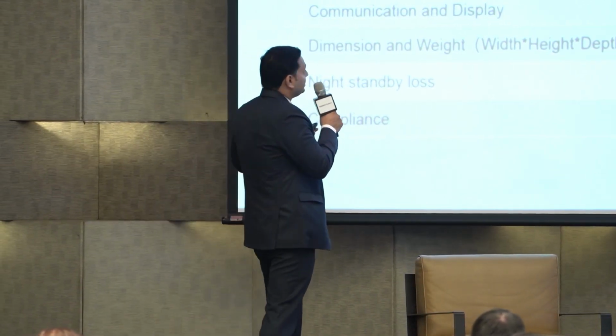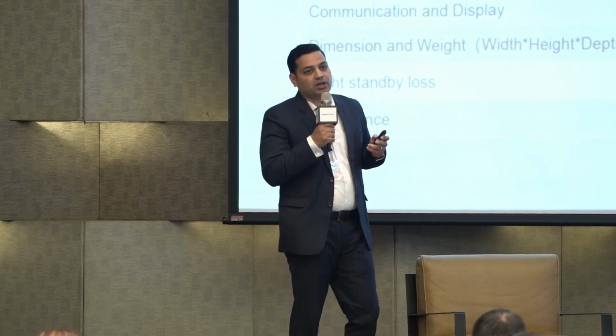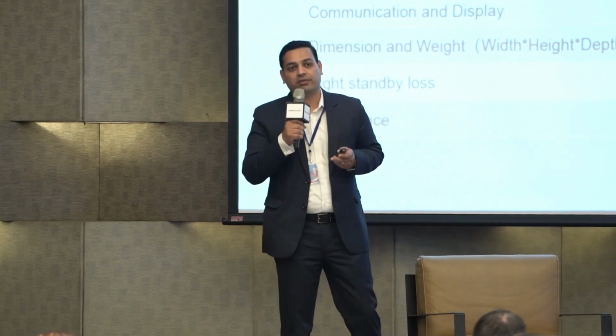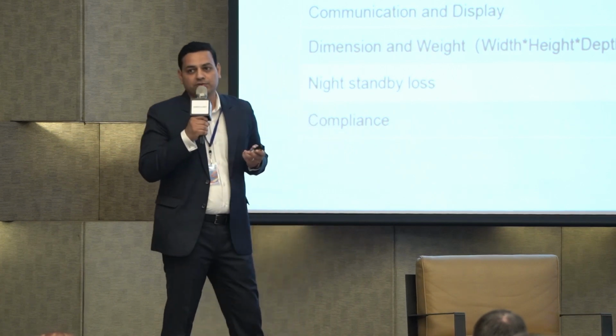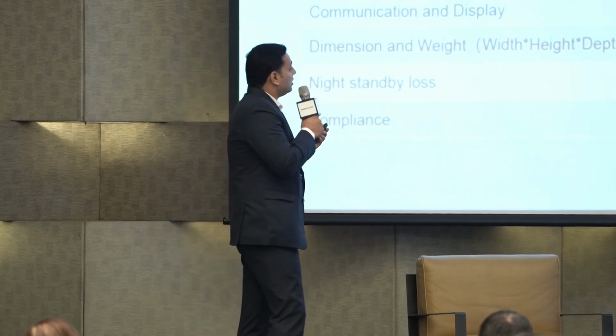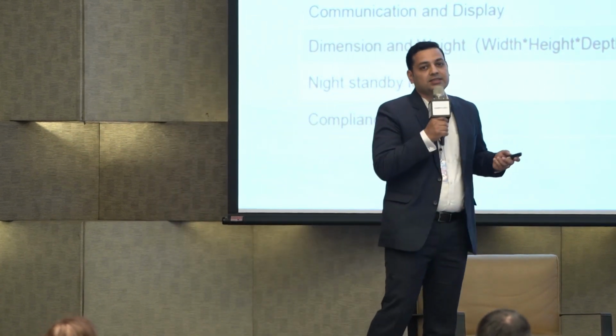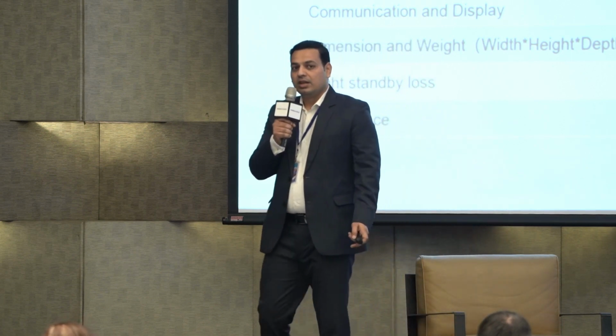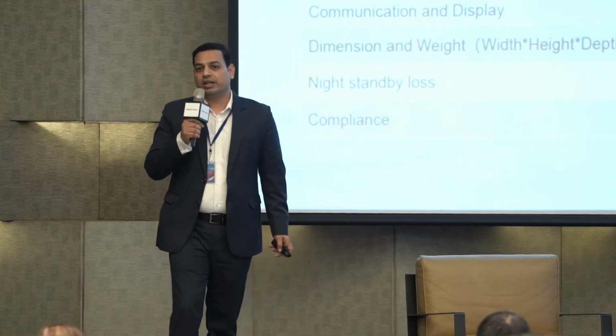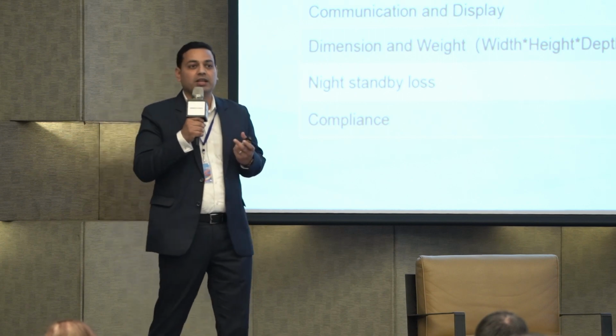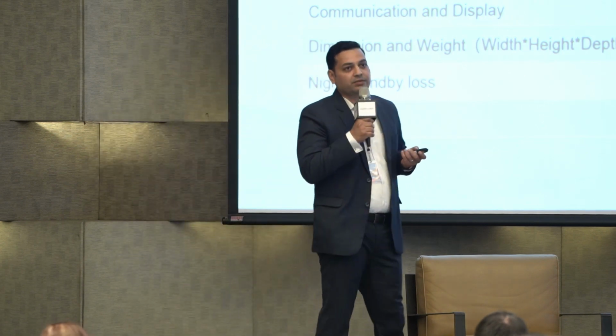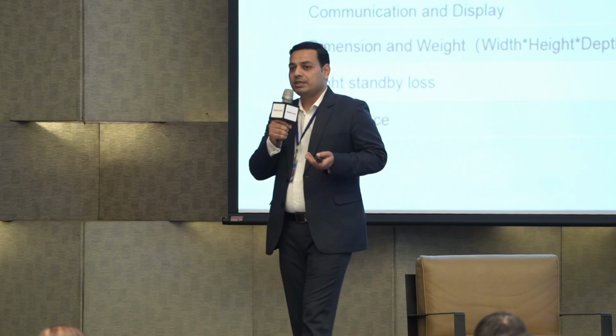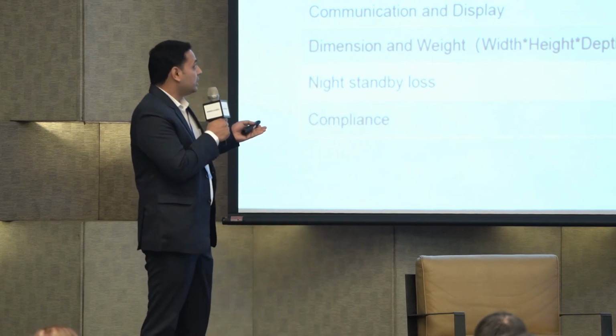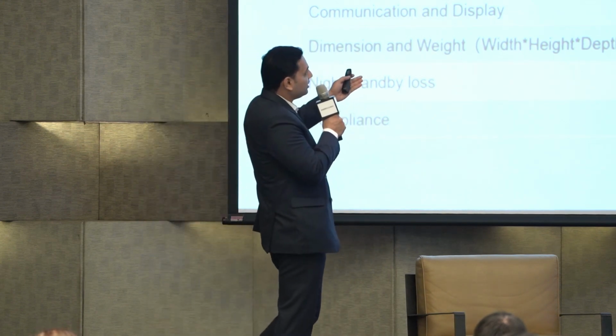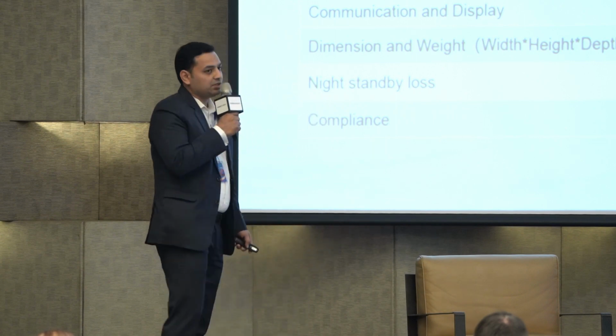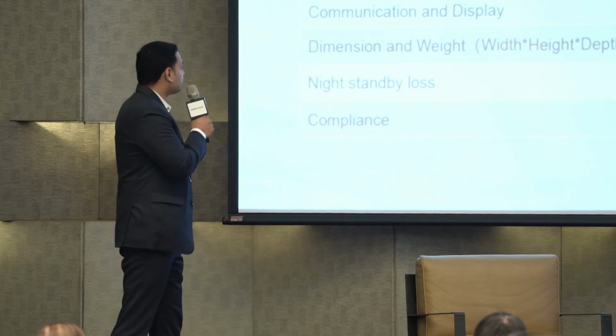Again, the degree of protection has two options, IP55 or IP65. Both are meant for outdoor uses. In this product also, we utilize IGBT 3-level topology, where we are able to reduce the switching losses of the IGBT and reduce the size of the LC filter, so that we can achieve the maximum efficiency from the product. That's why we are able to achieve 99% maximum efficiency and Euro efficiency of 98.7%.